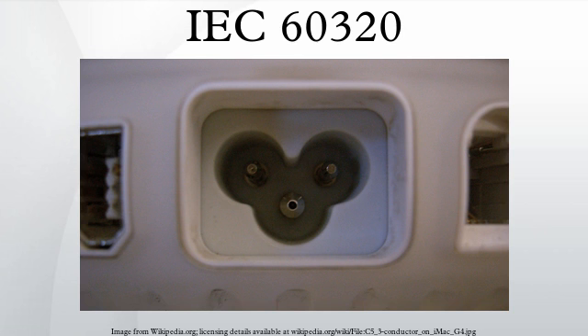Standards: parts of the standard. IEC 60320-1 specifies appliance couplers for household and similar equipment, two-pole couplers intended for the connection of a supply cord to electrical appliances. The female part connector supplies power to the male appliance inlet. The male part is designated by the even number 1 greater than the number assigned to the female part, so a C1 connector mates with a C2 inlet, and a C15A mates with a C16A.